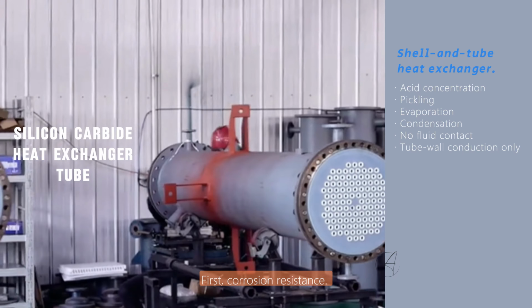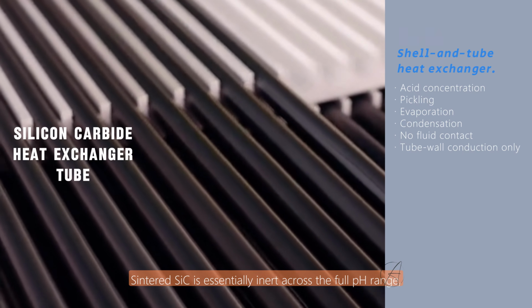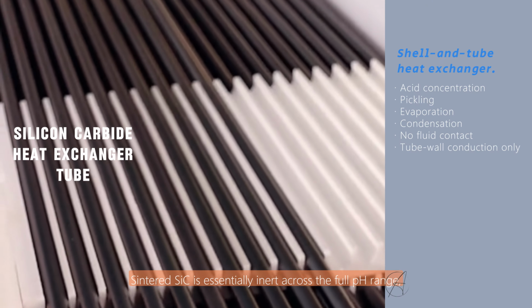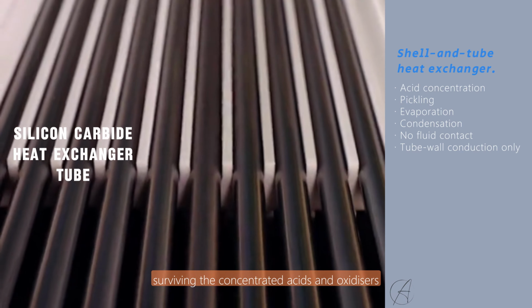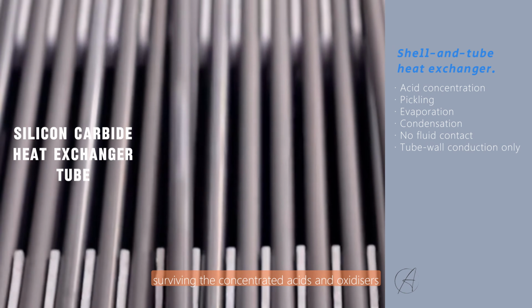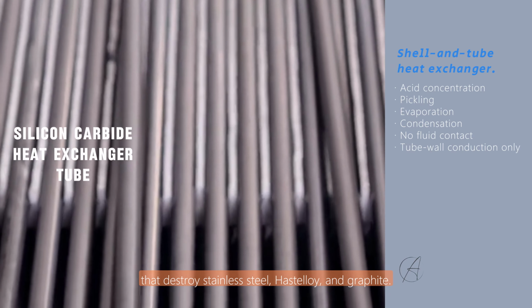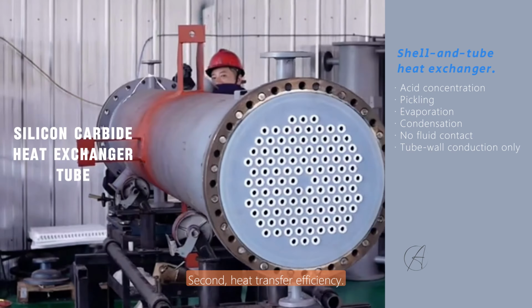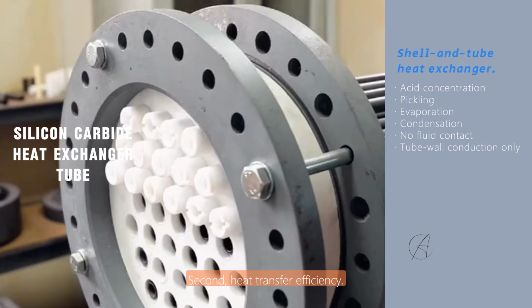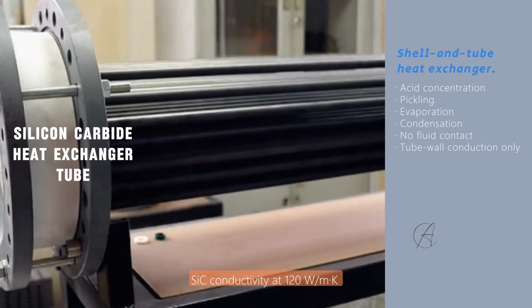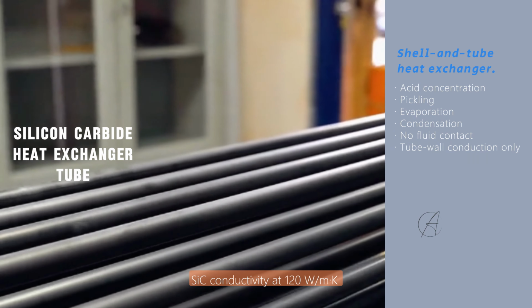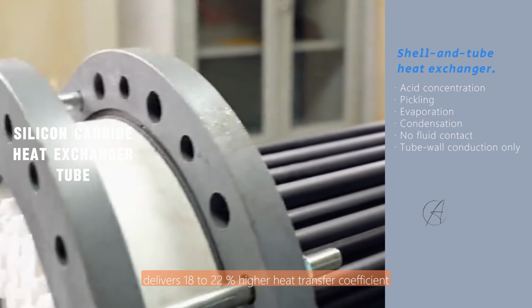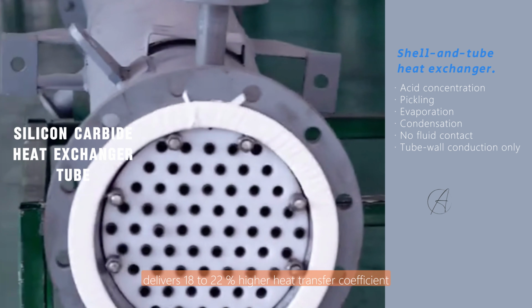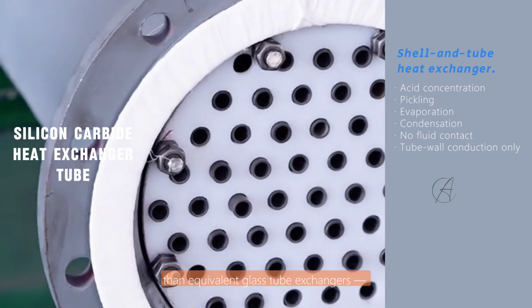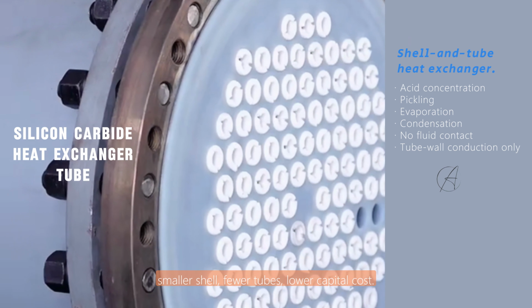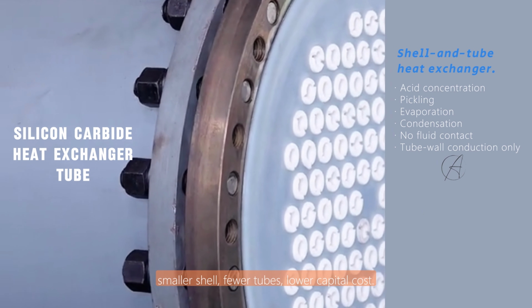First, corrosion resistance. Sintered silicon carbide is essentially inert across the full pH range, surviving the concentrated acids and oxidizers that destroy stainless steel, Hastelloy, and graphite. Second, heat transfer efficiency. Silicon carbide conductivity at 120 watts per meter per Kelvin delivers 18 to 22% higher heat transfer coefficient than equivalent glass tube exchangers, smaller shell, fewer tubes, lower capital cost.